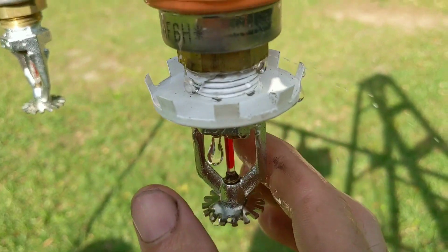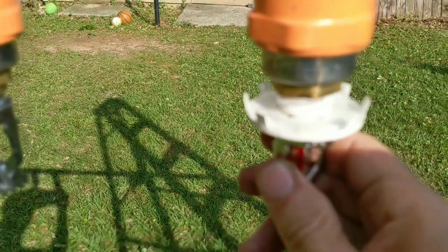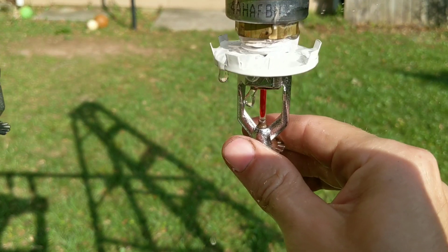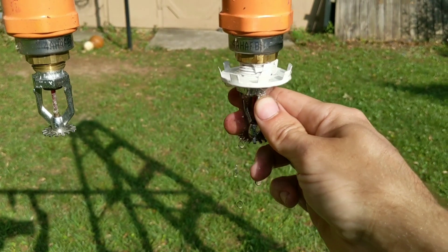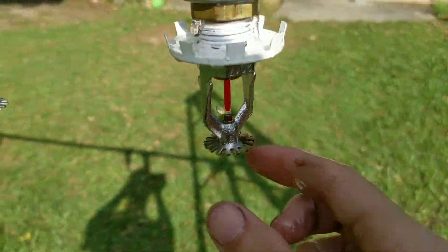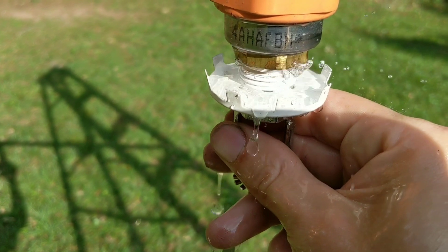We got something here — you see that right there? I cannot budge this sprinkler head. Look at that — it's pressurized, you'll see the water squirting out. It looks like sprite, it ain't right. That's a live system right there, that's what you're going to look for.